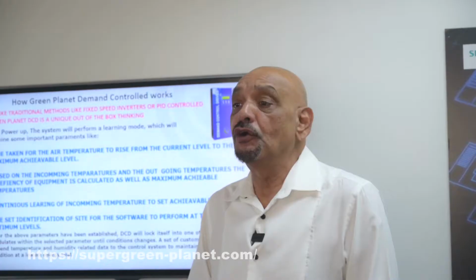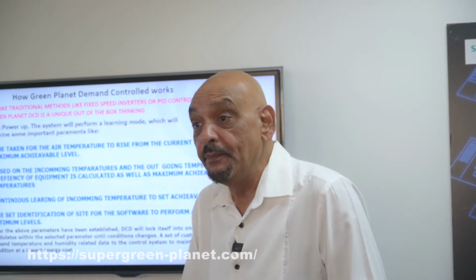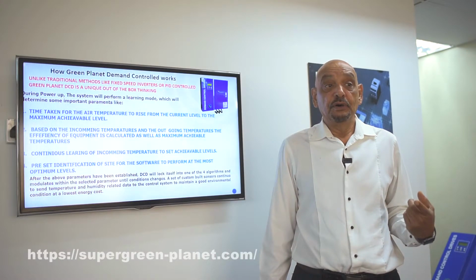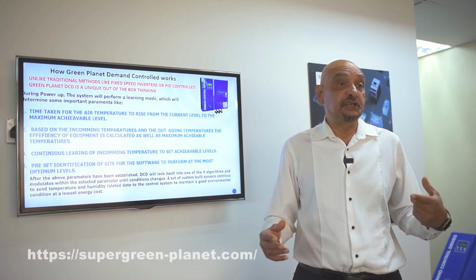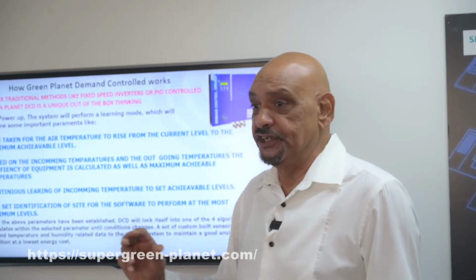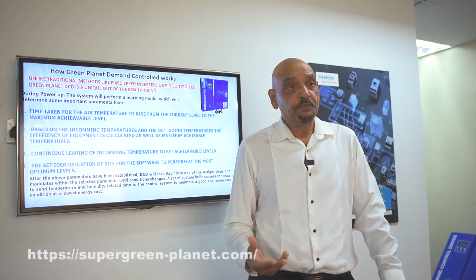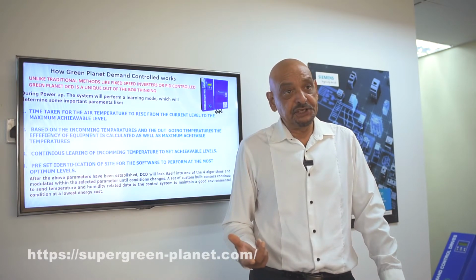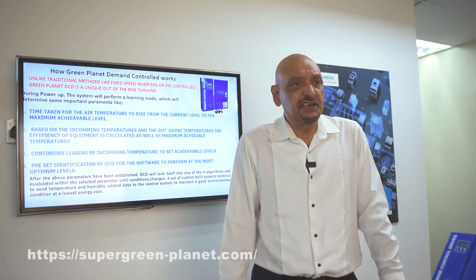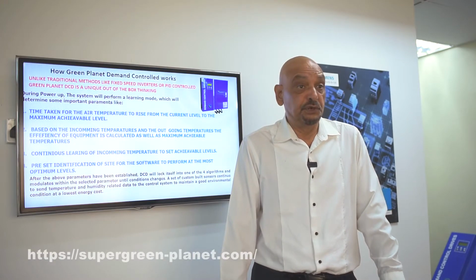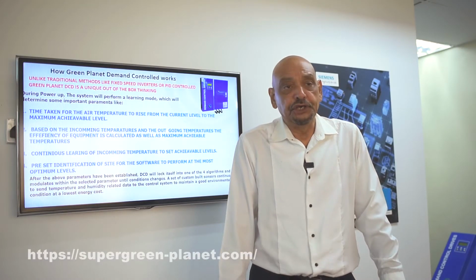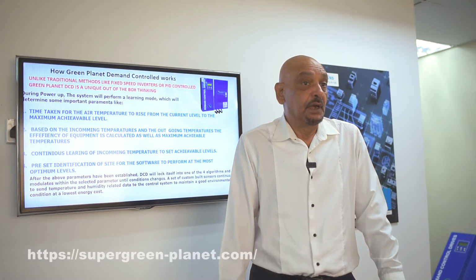The system will then automatically calculate and set to a level of frequency where the airflow is smooth. When the airflow becomes very smooth, both on the suction and the exit side, you have better airflow, you have cooler exiting temperatures, and at the same time, the noise level within your air handling unit would reduce by 50%. Once the system is already logged into one of these 4 algorithms, it will then continue to monitor the incoming temperatures as well as the RH levels in real time.